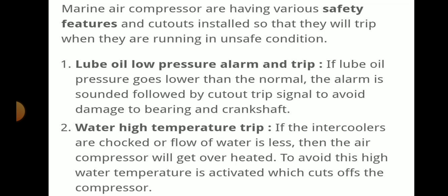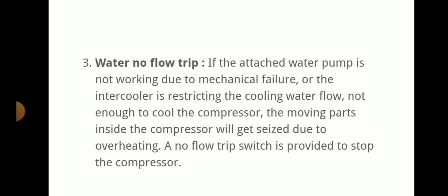Marine compressors have various safety features and cutouts installed, so they will trip when running in unsafe conditions. Lube oil low pressure alarm and trip means if lube oil pressure goes lower than normal, the alarm will sound, followed by a cutout trip signal to avoid damage to the bearings and crankshaft. Water high temperature trip means if the intercoolers are choked or the flow of water is less, the compressor will get overheated. To avoid this, the high water temperature trip is activated, which cuts off the compressor.